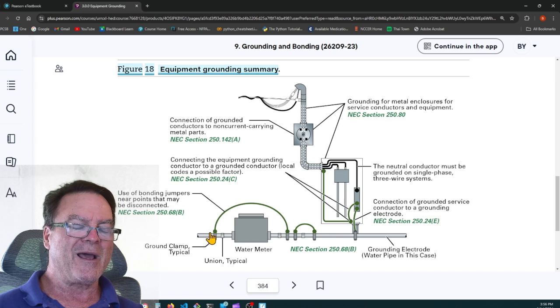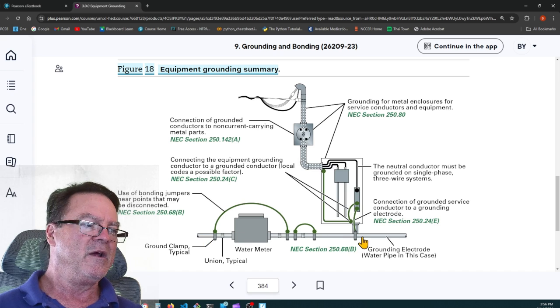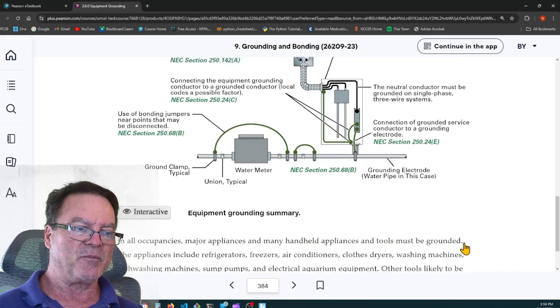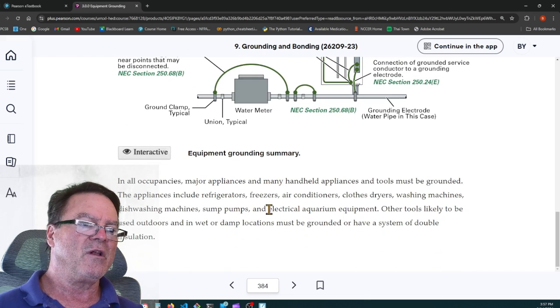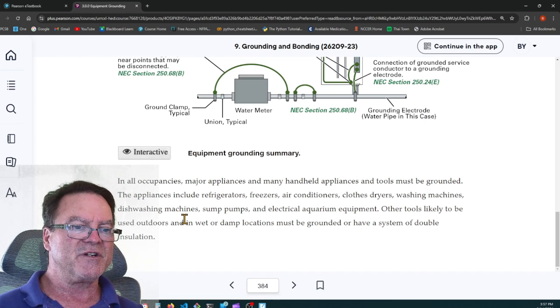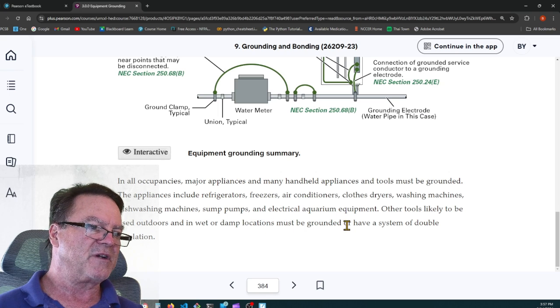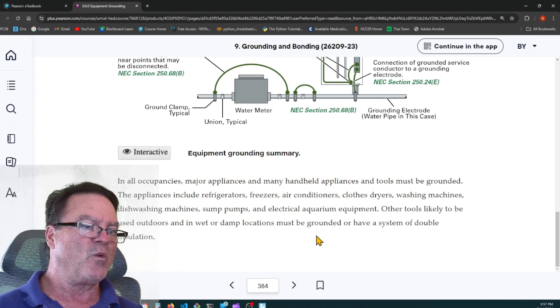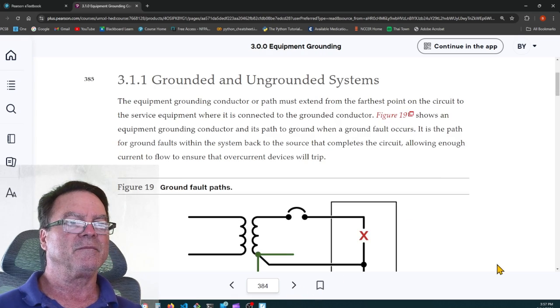But the water pipe cannot be the sole grounding electrode. That's why we have to have a supplemental ground rod when you have a cold water pipe as the grounding electrode. You have to have a supplemental grounding electrode. It says in all occupancies, major appliances, many handheld appliances and tools must be grounded. Appliances include refrigerators, freezers, air conditioners, clothes dryers, washing machines, dishwashing machines, sump pumps, and electrical aquarium equipment. Other tools likely to be used outdoors and in wet or damp locations must be grounded or have a system of double insulation.